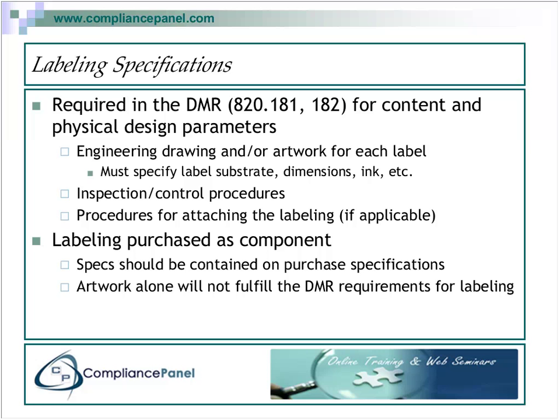This is hugely critical when you're putting your labeling on the Tyvek side of a product that's going to be sterilized, because if you misplace the labeling or it's done in the incorrect area, or if it's supposed to go on the transparent side and it goes on the Tyvek side, this could adversely affect your sterilization.